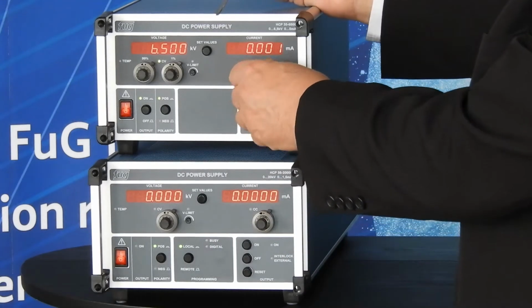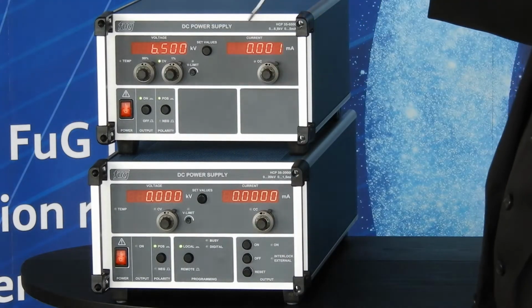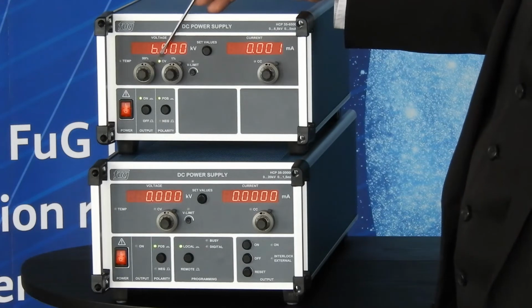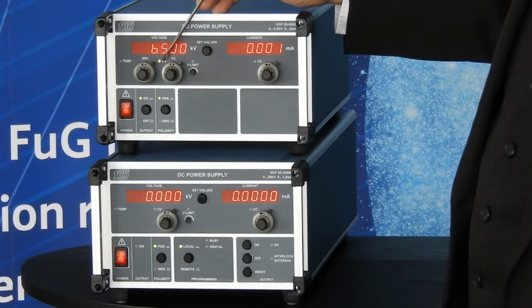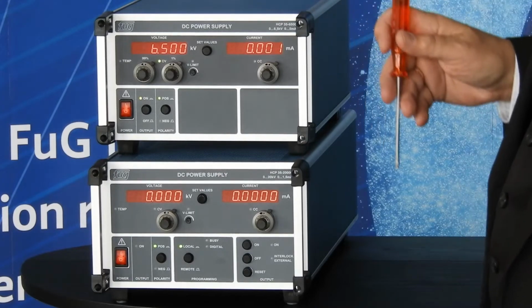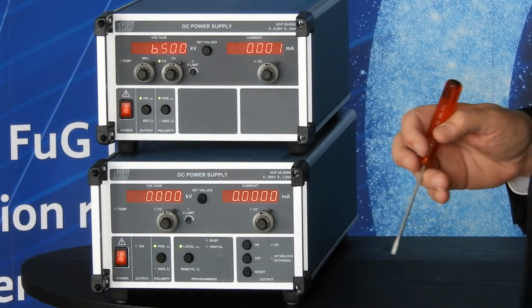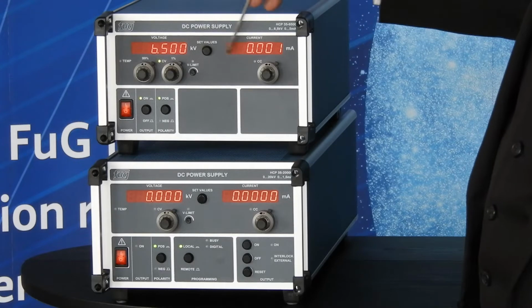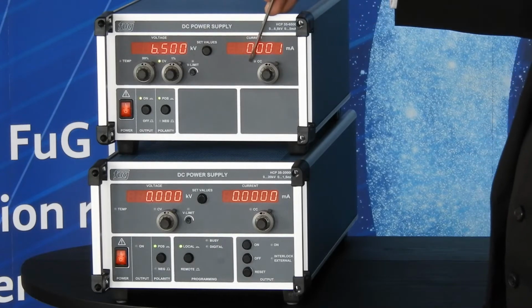The power supply now tries to hold the current constant at 0, not the voltage. Now, when I give some current, the power supply goes into constant voltage mode again and the CV LED is on. If the power supply is operating normally, always one of these two LEDs should be on.